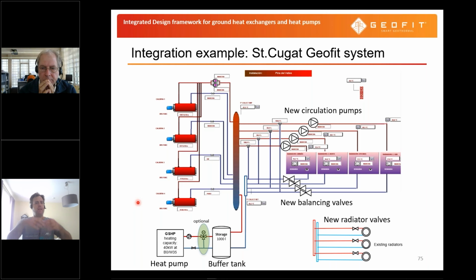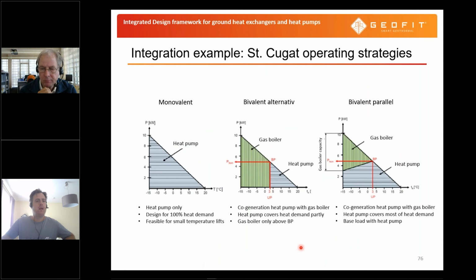But there are things to take care of, not only the heat pump. It's more than just placing a heat pump in an existing system. You need to take a careful look at the flow rates and at your hydraulics in order to have an efficient operation. And this is what Henk showed at the beginning of this training, that the operating strategy plays an important role. So Henk already showed you this with those 3 operating modes.